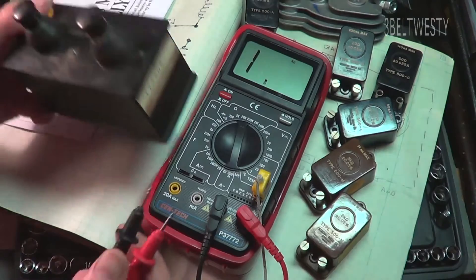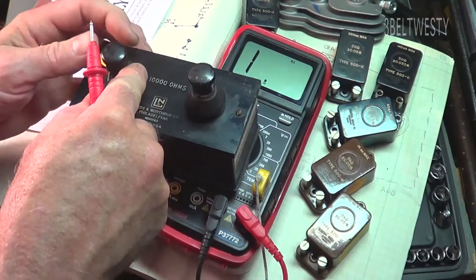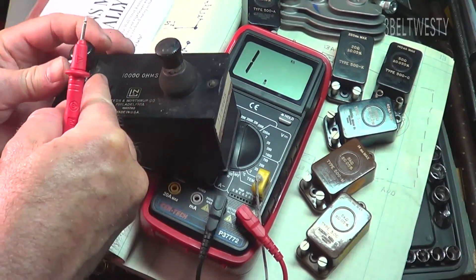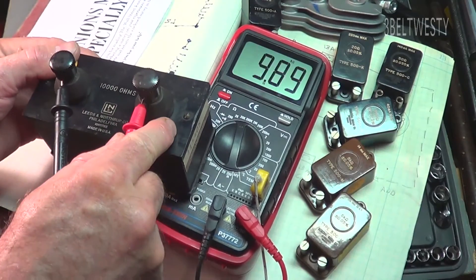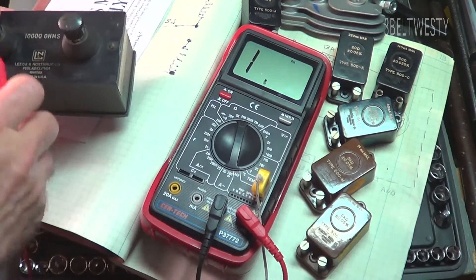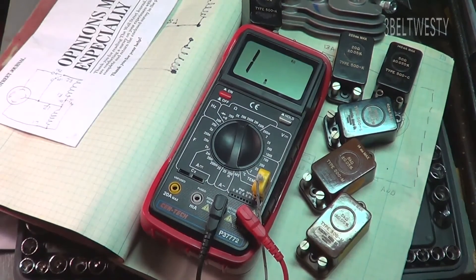Here's a 10K Leeds & Northrup standard — go ahead and tighten this one on. Here's 9.89, so the Harbor Freight meter is fairly accurate — actually very accurate.